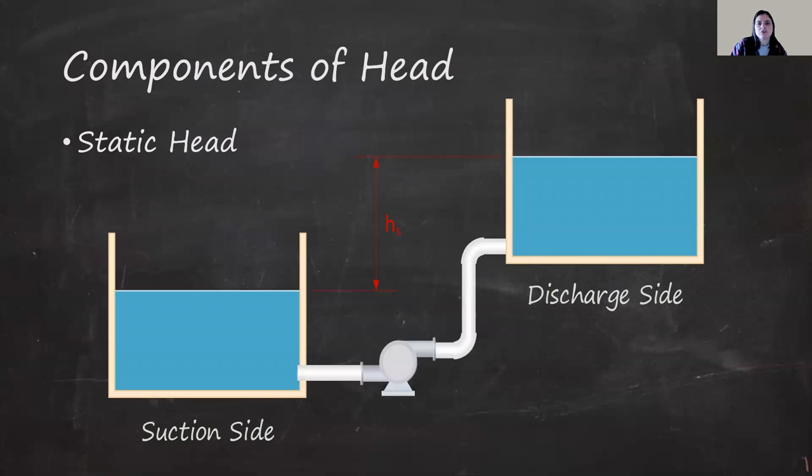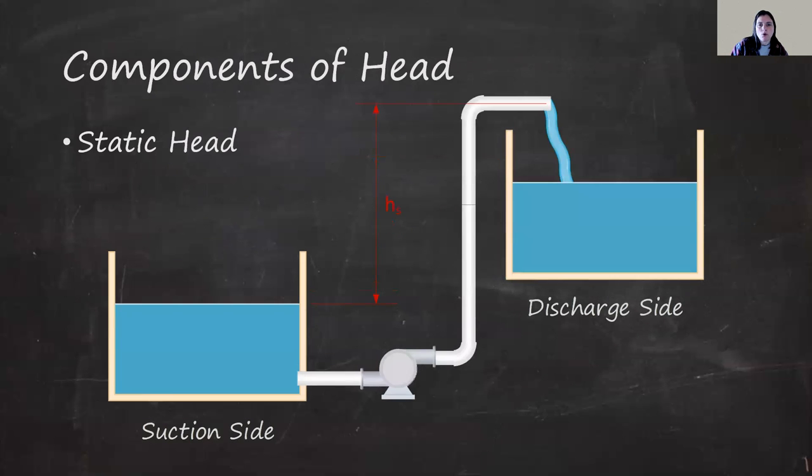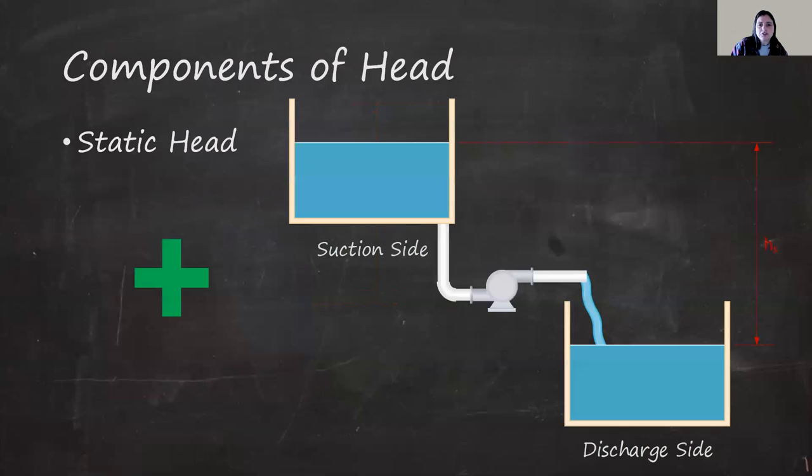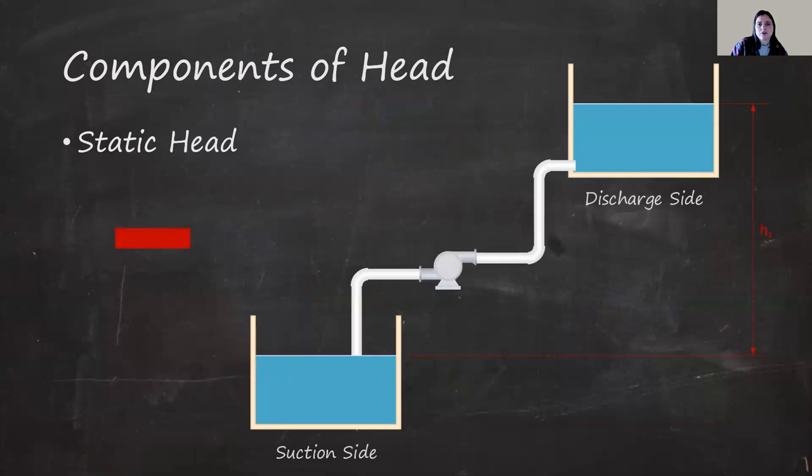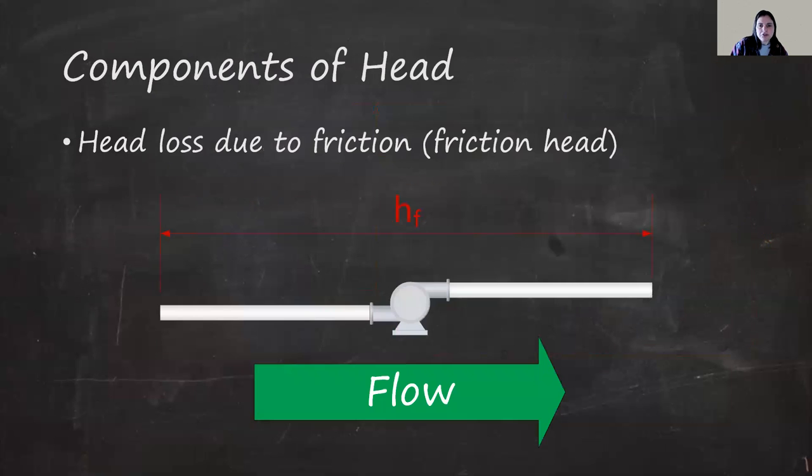Total dynamic head is determined by adding the head from contributing components. Static head is the difference in elevation between the surface of the water on the suction and the discharge side. Or, in the case of free-flowing fluid, the height of the exit. Essentially, static head factors in the weight of fluid and gravity. Water that can move with the help of gravity increases pressure and aids the pump. While moving against gravity works against the pump and requires more energy.